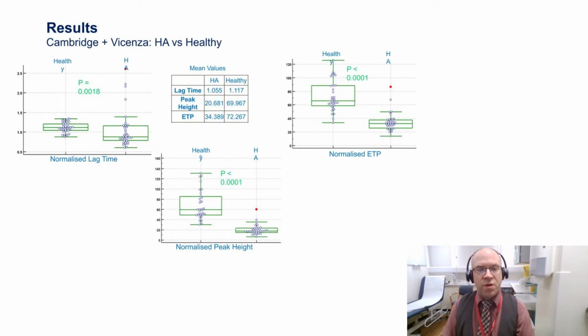So moving on to the comparisons of haemophilia A against healthy, we can see here, using the box plots, that using normalized parameters, which were used for the analysis throughout the study, because it was found that normalizing them against the standard plasma used as part of the assay reduced the imprecision within the assay significantly and led to much more acceptable CVs.